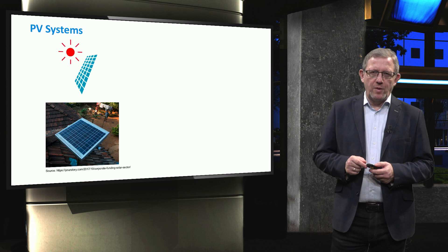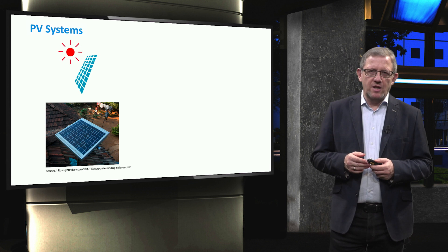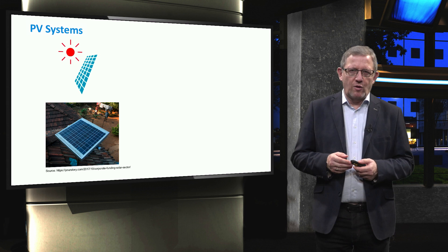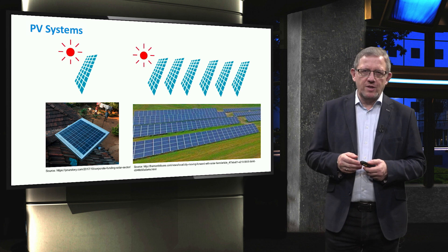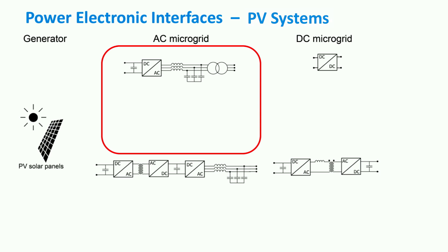The first component for which we introduce its power electronic interface will be photovoltaic systems. As shown in the slide, at a smaller scale at low voltage level, rooftop PV systems have many applications like off-grid remote villages. For these low-voltage applications, typically one single converter may adequately step up the voltage in one stage. However, for medium-scale PV system farms up to a few megawatts connected to medium voltage levels, the DC voltage might be stepped up in a number of conversion stages using more complex converter topologies and AC transformers.